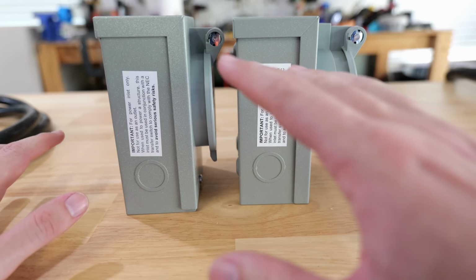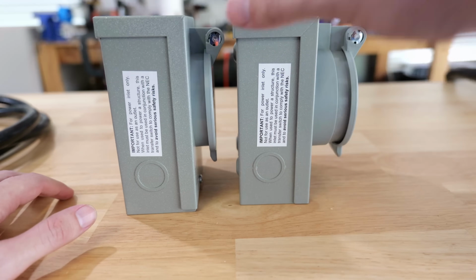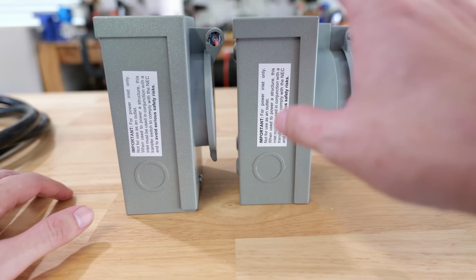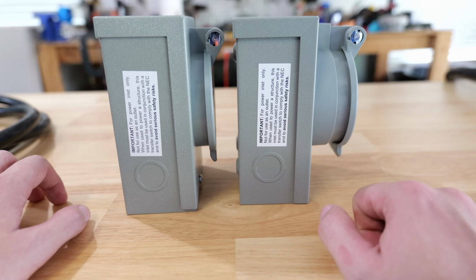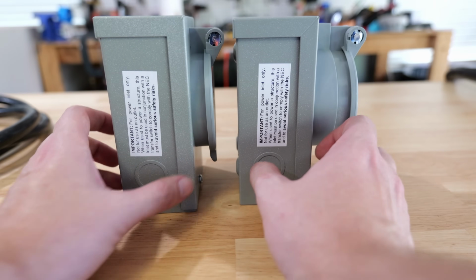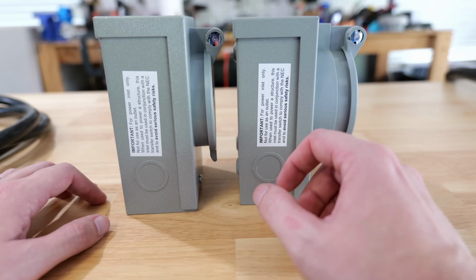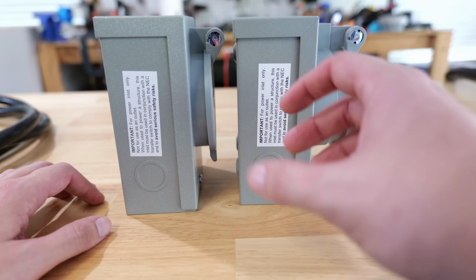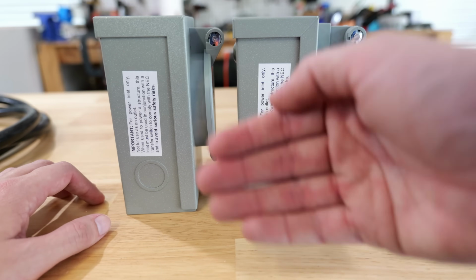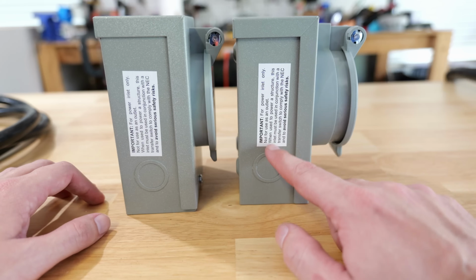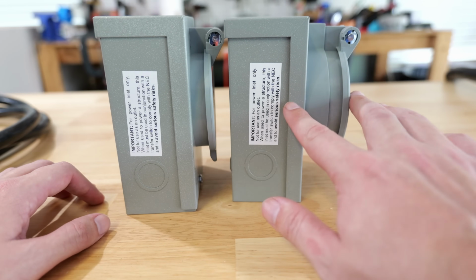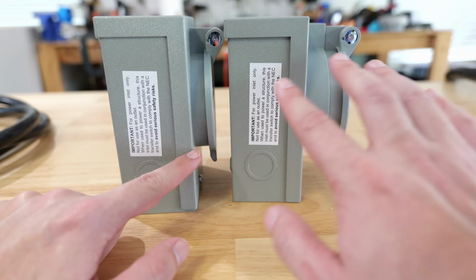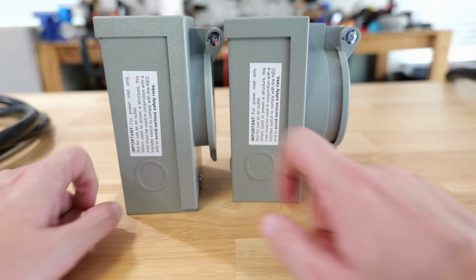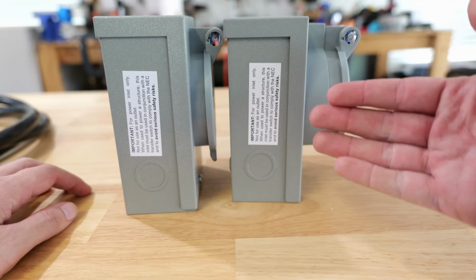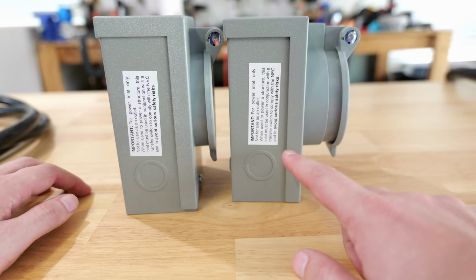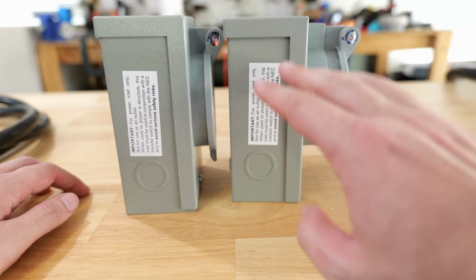Also, something to note that Reliance finally fixed, and why I did not buy a 50 amp Reliance box last time I bought one, was because you can see how small these boxes are. And when you're working with number 6 wire, it's really hard to handle and be able to fit it all in the box, or at least the amount that you would need to be in the box. But they have since then extended, as you can see, the face of this sticks out further on the 50 amp than on the 30 amp. So this is giving a little bit more space inside of this 50 amp to be able to work with those bigger wires.